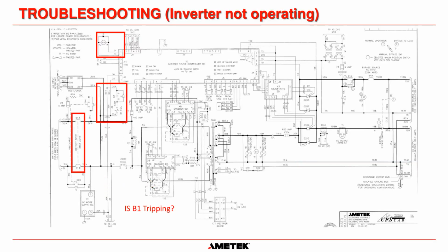So what our system does is it monitors the 135 volts at that pin there. And if that goes below 105 volts DC, then this board here says, okay, I'm going to disconnect the battery, and it sends a signal out on these two terminals here to K4, the coil of K4. And the K4 contacts are here, and they're connected in series with the B1 coil here, which is this breaker here. So if we send a signal, we energize K4, K4 closes, we energize using the battery power the coil, and the coil shunt trips the input breaker at 105 volts.